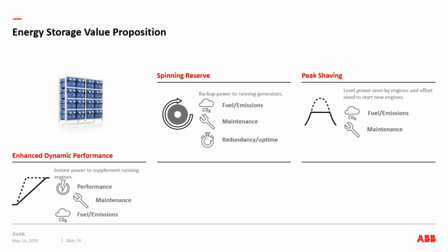The third is enhanced dynamic performance. Diesel engines can certainly respond when you need them, they'll ramp up relatively quickly, but they don't like to. Diesel engines like smooth, slow increases and decreases in power demand. So when they're asked to ramp up or down very quickly, you'll have visible emissions, the engine won't operate as efficiently as usual, and it could dirty your cylinders. So letting the battery take those quick swings in power demand, while the generators keep operating at a relatively constant power and slowly ramp up at the speed they'd prefer, offers a lot of benefit to engine efficiency and maintenance, and also delivers much better performance for the operator through faster response times.